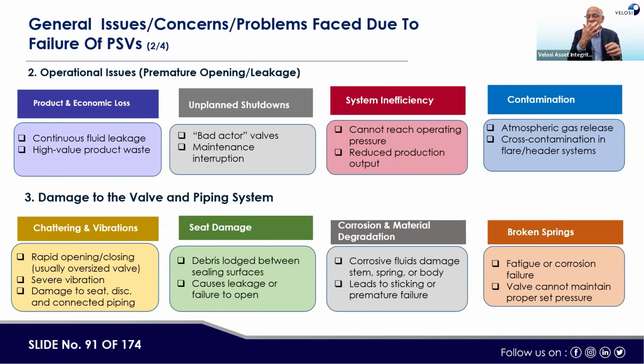Third, what could be the case? The PSV is stuck, not opening. It means the PSV is not opening and the pressure is going high and then it may rupture. So we have to see consequences in the same angle. If the PSV is prematurely popping, product wastage. If the PSV is not lifting at set pressure, there could be explosion, there could be a rupture. If the PSV is lifting at set point, this is the main purpose of the PSVs, and a PSV may also leak.